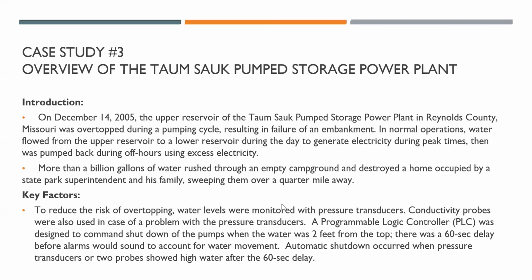So what did happen? To reduce the risk of overtopping, water level was monitored with pressure transducers. Conductivity probes were also used in case of problems with the pressure transducer. A PLC was designed to command the shutdown of the pump.